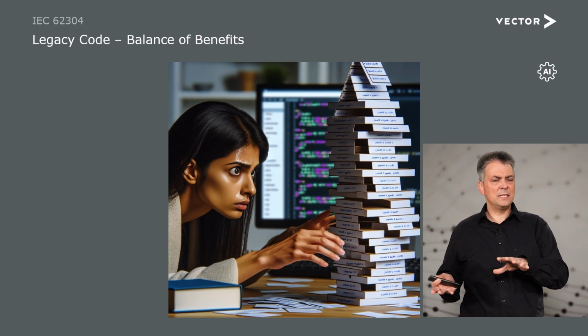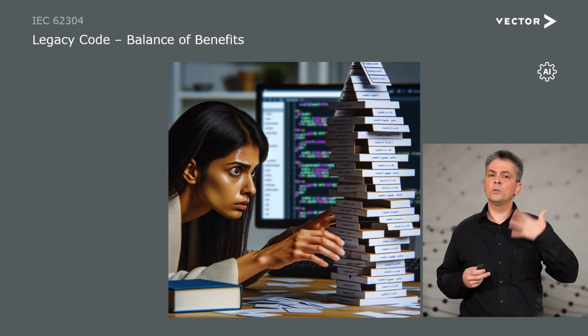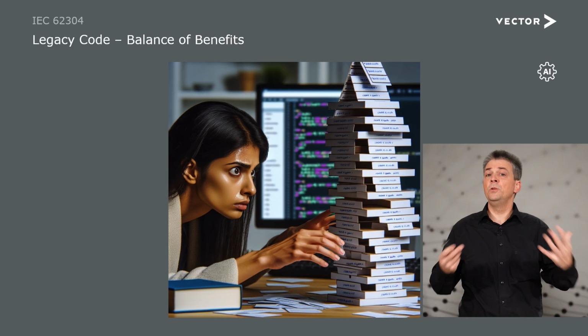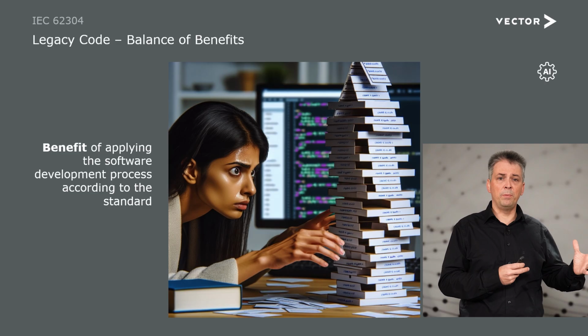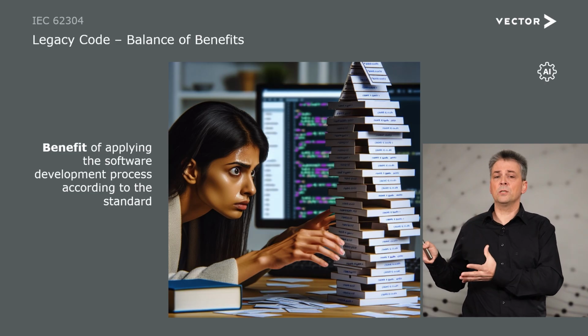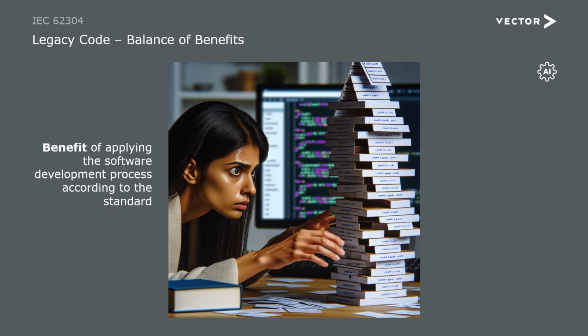When you deal with legacy for medical device software, if you want to put a new device on the market, develop new software, then you have to balance the benefit of applying the software development process according to the standard against the risk of introducing new defects by modifying the existing code.